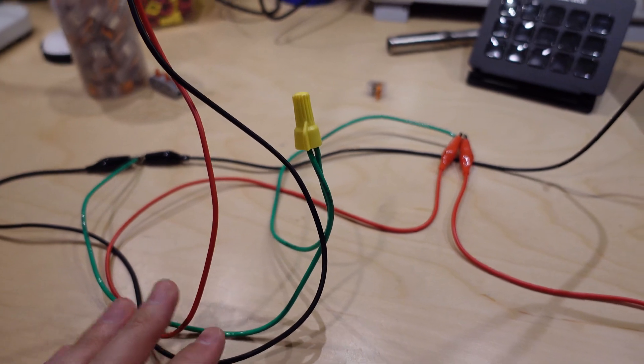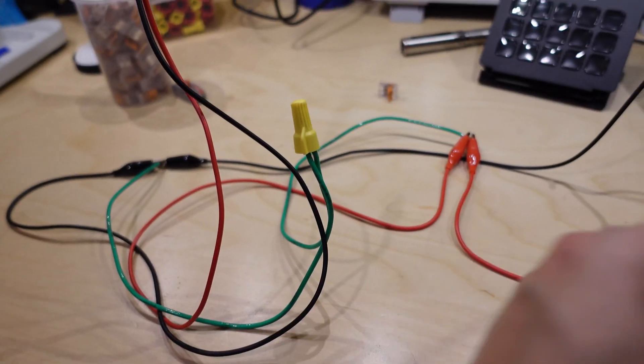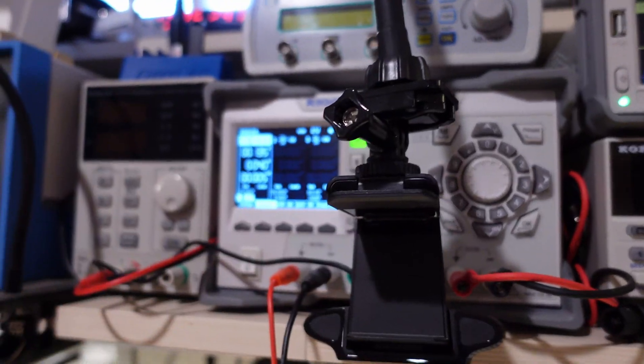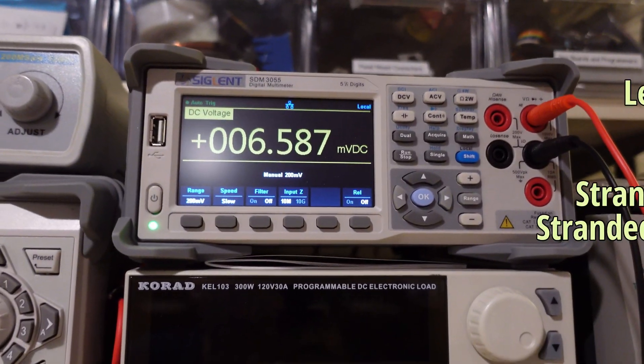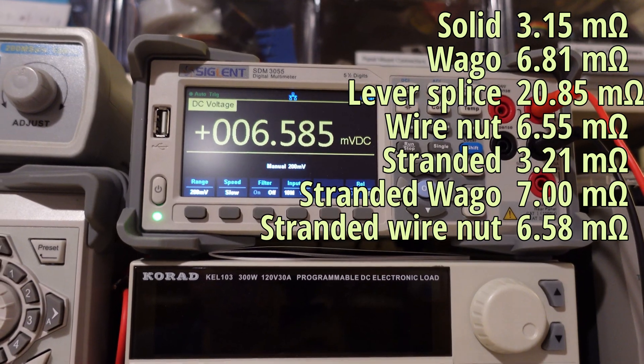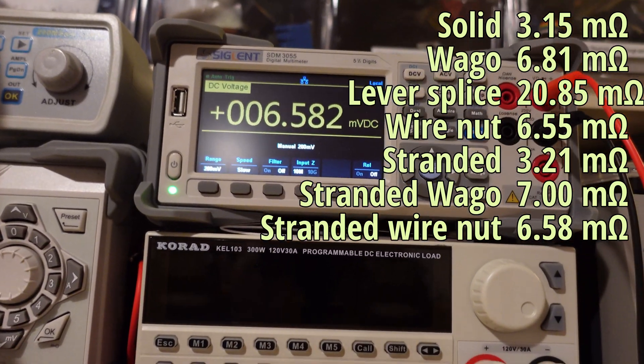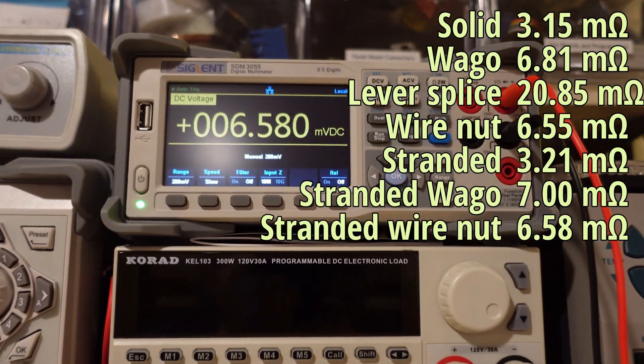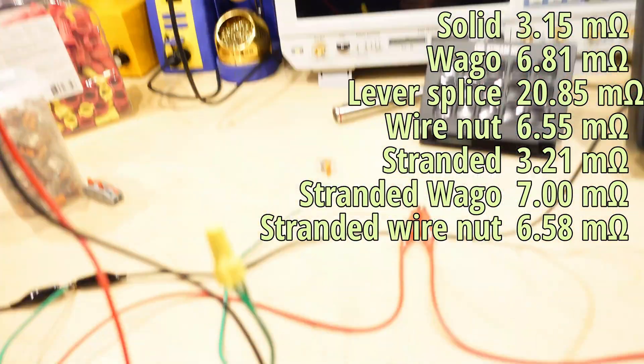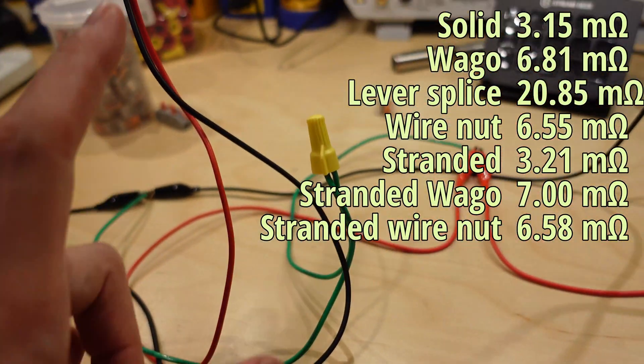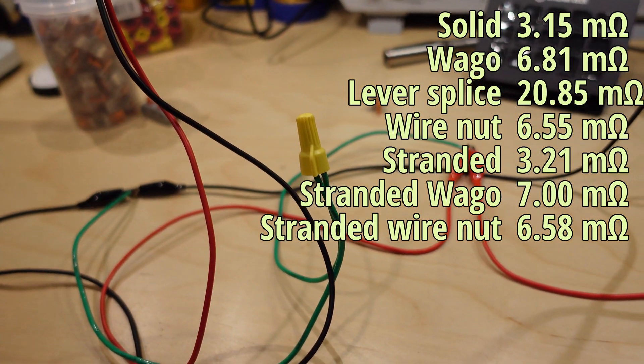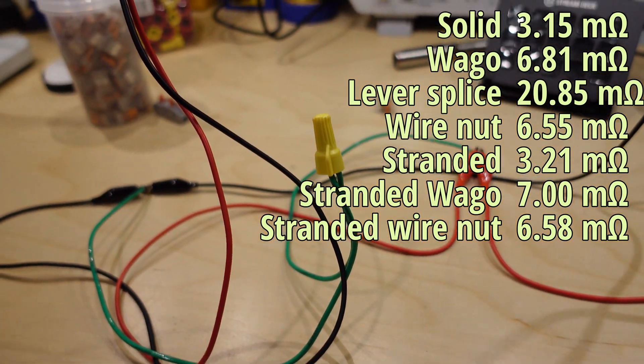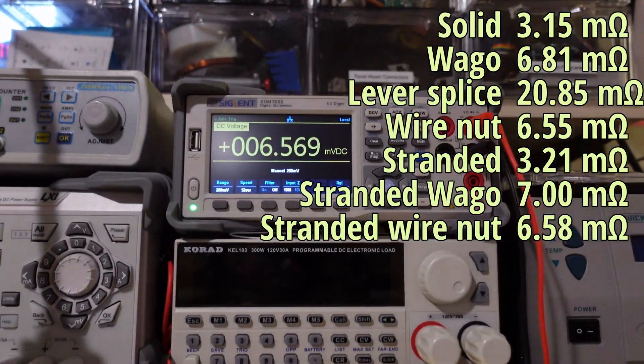For you, my internet friends, I sacrificed a brand new wire nut. This is the one I used last time because somebody's going to say you're not supposed to reuse those. So one amp. Now we're getting 6.58 something. I don't remember what the one was with the solid wire, but this is a very good connection. So there you go. Seems like wire nuts actually provide a slightly better connection than the WAGOs, but it's almost irrelevant and doesn't seem to make a big difference whether the wire is solid or stranded.